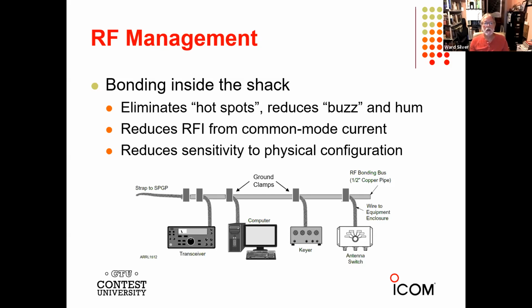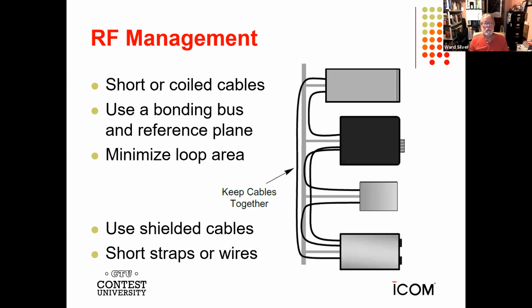By bonding everything together, you have 0 volts between point A and point B, so you have 0 current between point A and point B, or at least minimal. And it also reduces sensitivity to physical configuration, so you can move the equipment around and suddenly you don't have crazy business going on at 15 meters. You want to use short or coiled cables. Use the bonding bus and the reference plane to establish that common voltage for everybody. You minimize the loop area because the bigger the loop, the more voltage is going to be induced in the loop. Keep your cables together. Run them along your ground connections and the bonding bus. Always use shielded cables even for power, and use short straps or wire.